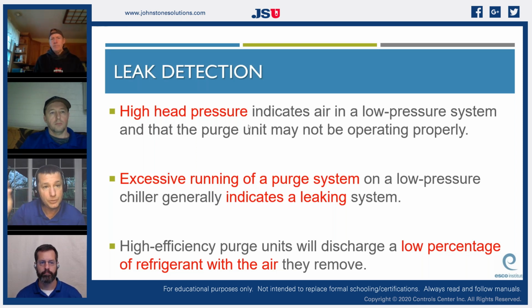When it finally separates the air and releases it, it's going to take a purge valve and open, and release that air back out into the atmosphere. So what we're looking for is how often that purge valve has to open. We can start graphing that and trending it, because the more frequently that thing starts popping, the larger the leak we know that we have.